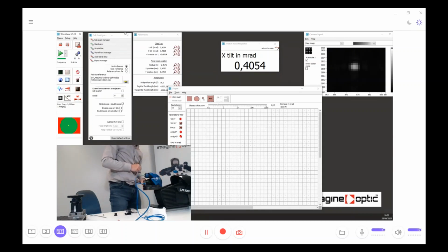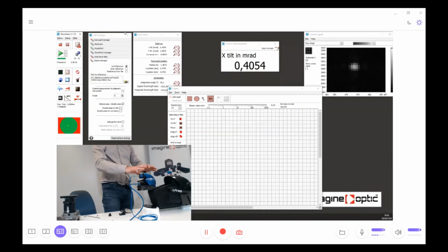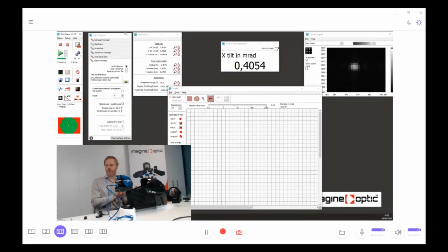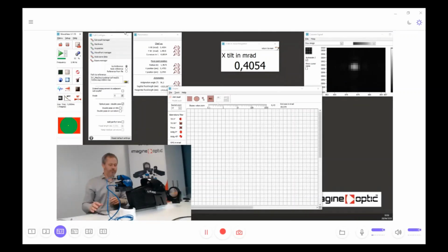Yeah, it is correct now. As you see, this system allows you to replace the R-FLEX exactly at the same position. As you see also, it's a question of minutes. I just changed the setup. I was measuring converging lenses, and now I'm ready to do measurements on flat glass, zero power transmitted glass.